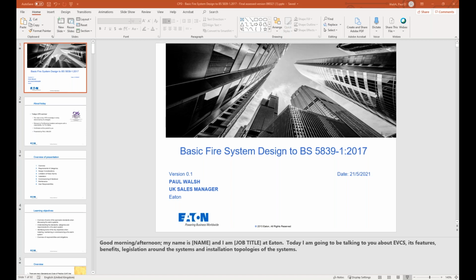These clauses are sometimes a bit too much detail for what we're going to cover today, but they're definitely something to be aware of. So if you are linking into other systems, whether that is extinguishing systems, gas suppression, holding open fire resisting doors or opening locked doors on escape routes with access control systems, shutting down AC, or smoke vent control, and grounding lifts if there are any. As I said earlier, BS 7273 is another massive document, and part of that is to do with things like door holders and how they should operate when linked to a fire alarm system, and that's for another day.